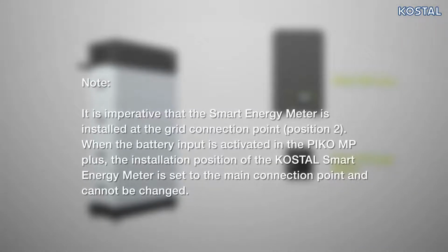Note: it is absolutely essential that the Smart Energy Meter is installed at the grid connection point, position 2. When the battery input in the PIKO MP Plus is activated, the installation position of the KOSTAL Smart Energy Meter is set permanently at the grid connection point and cannot be changed.